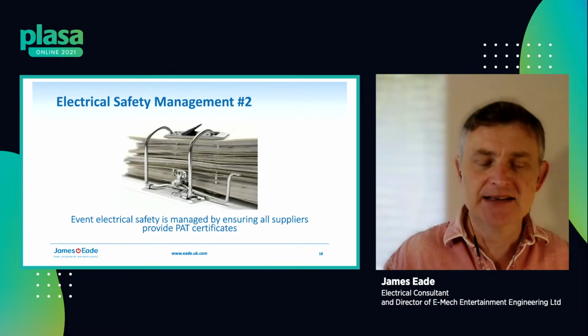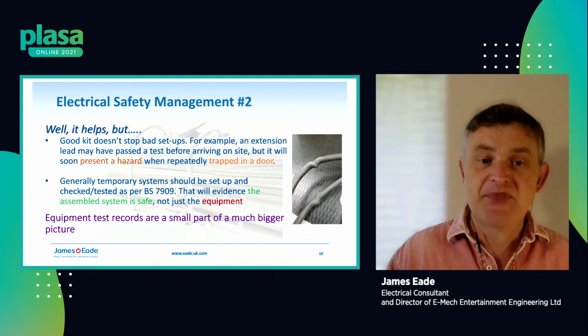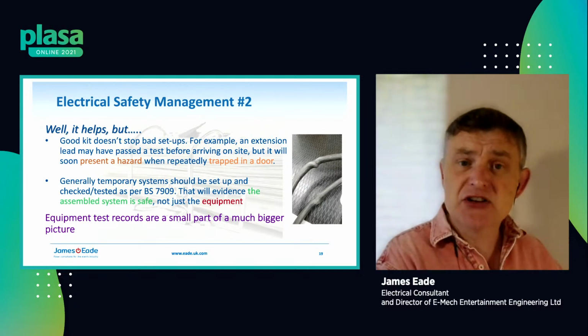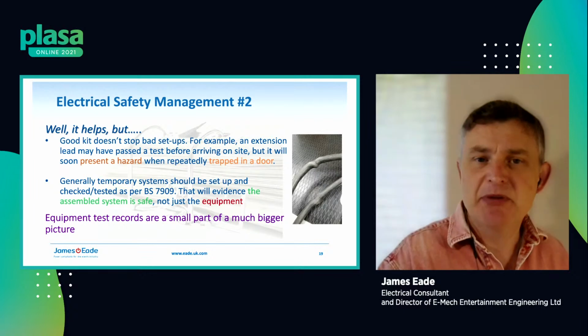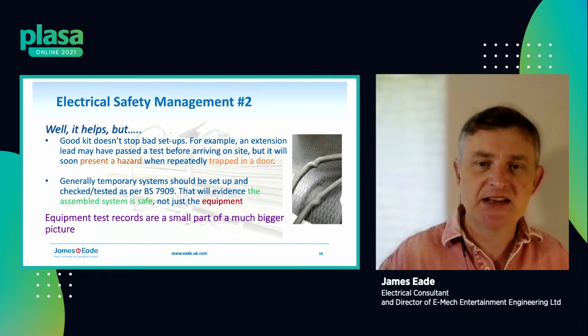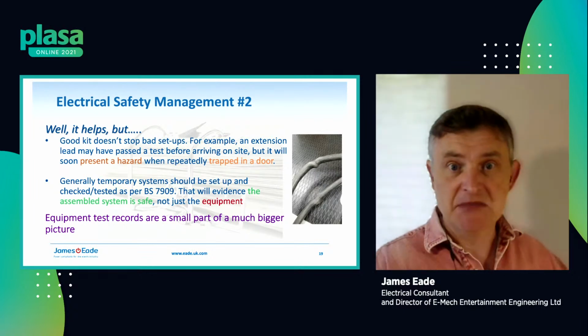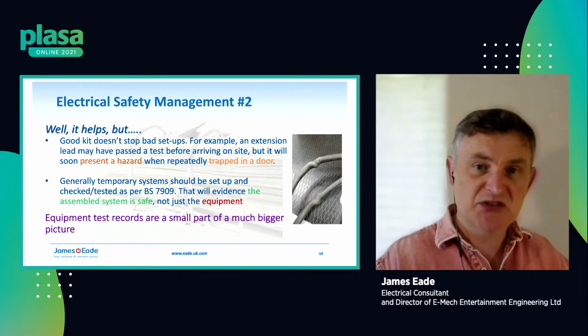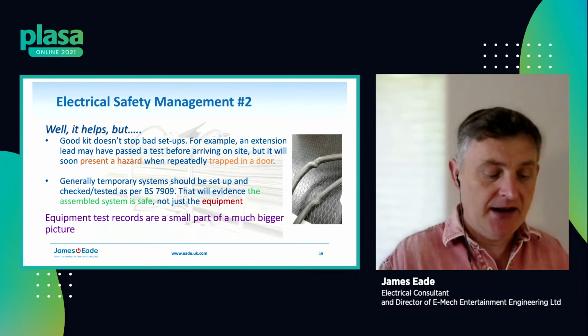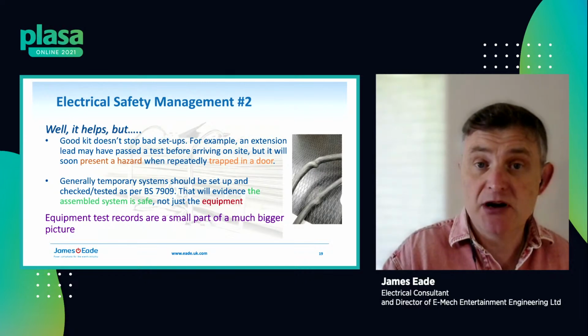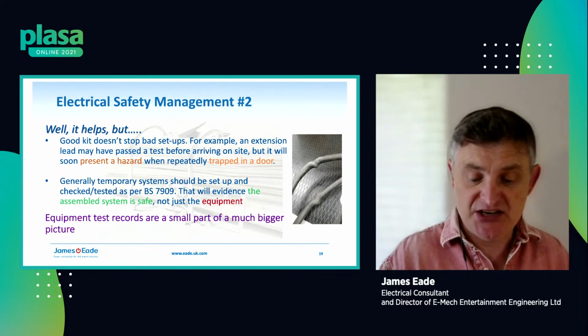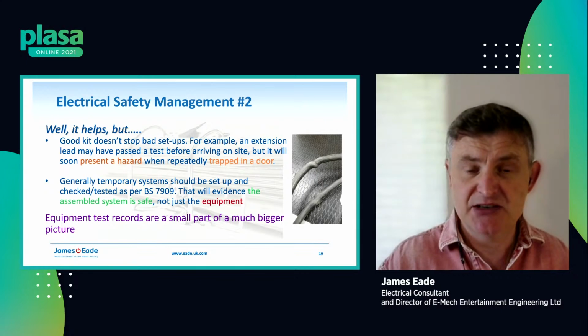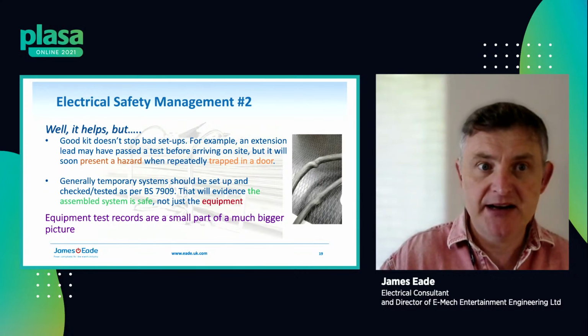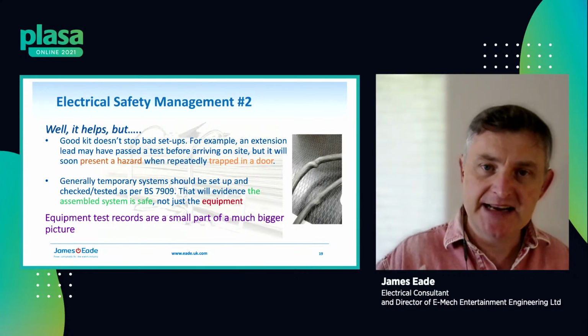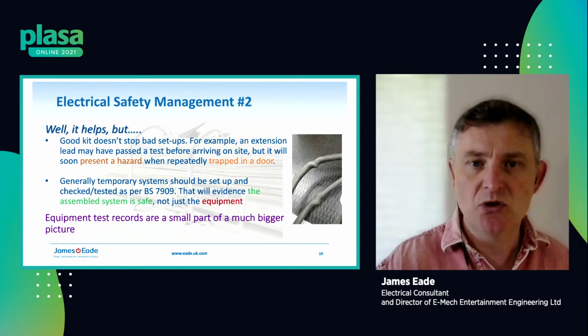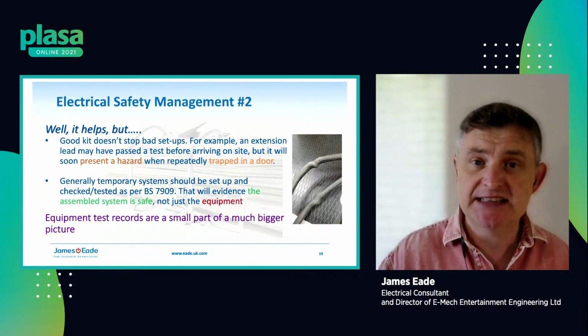So if we go to the next slide, what we'll see is that having good equipment is lovely, but it doesn't stop people setting it up in a bad fashion. So I might have a perfectly lovely 63 amp extension lead running from stage to front of house, and it was tested before it arrived — all looking shiny and new, good insulation resistance, good continuity, etc. But if I route it by a door and it keeps getting chafed and the insulation gets worn away, then it's going to present a hazard.